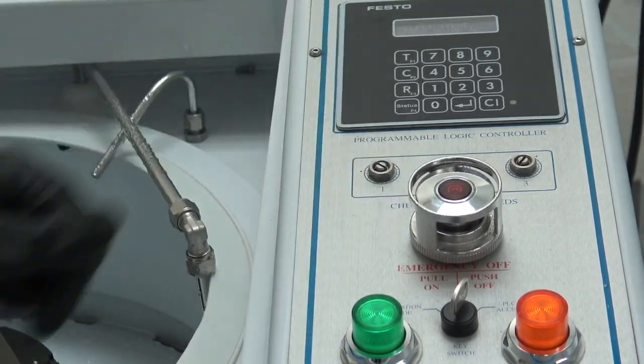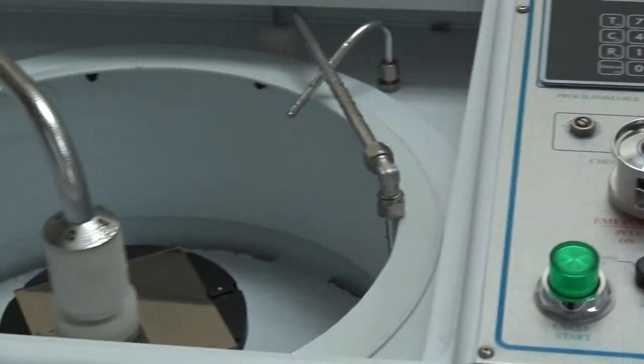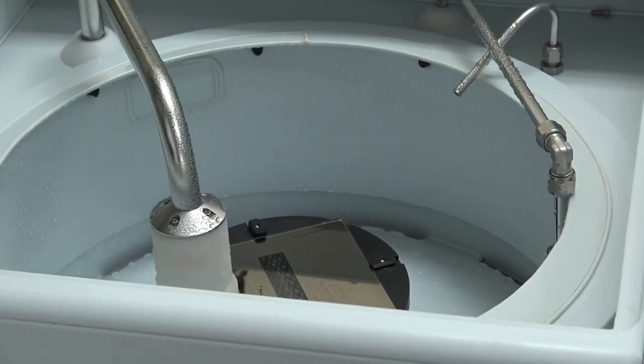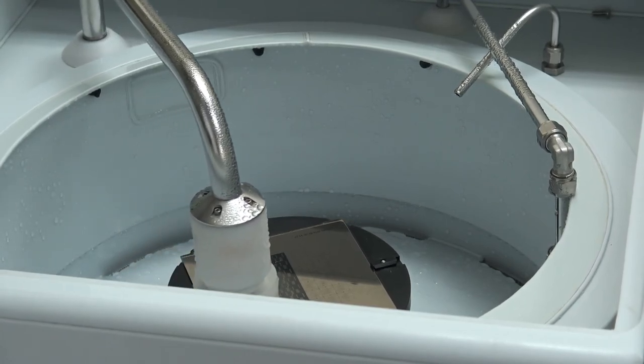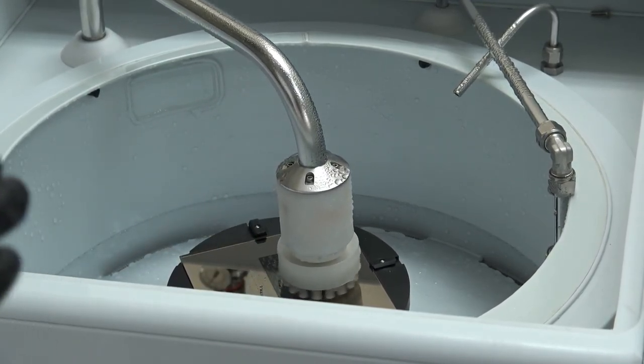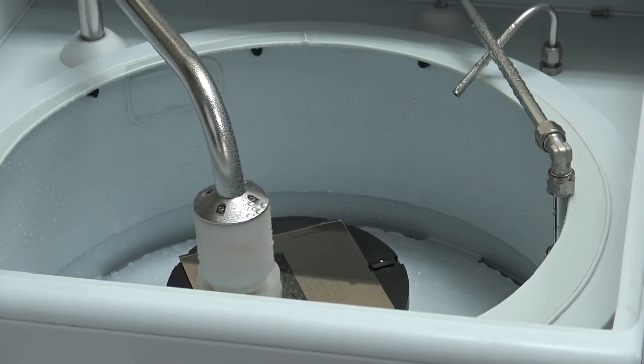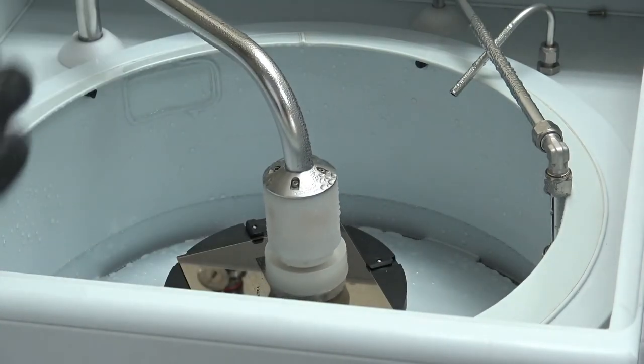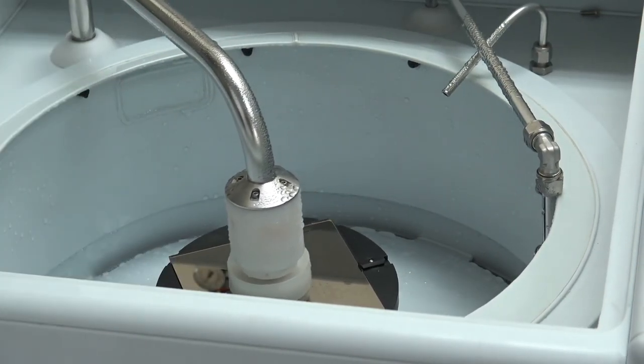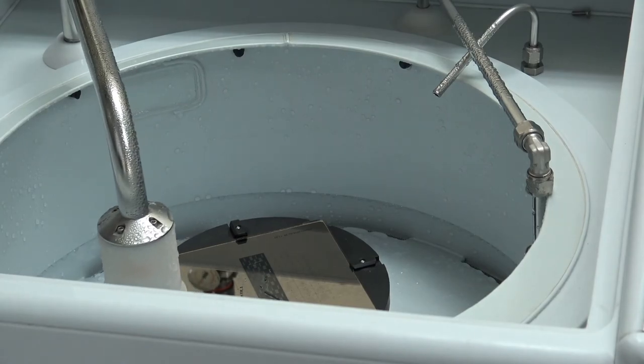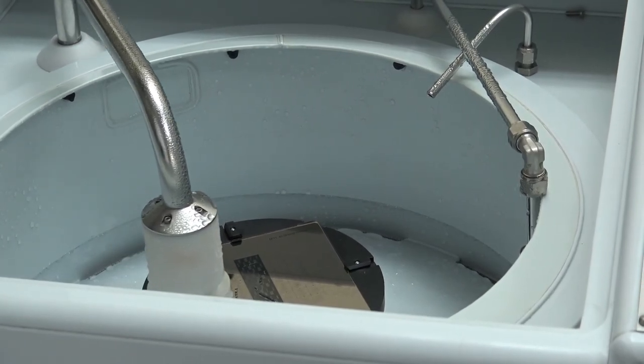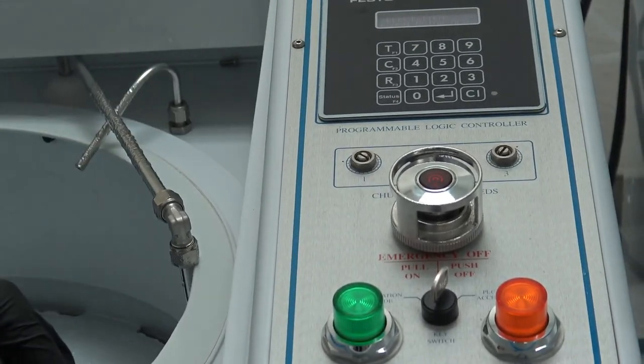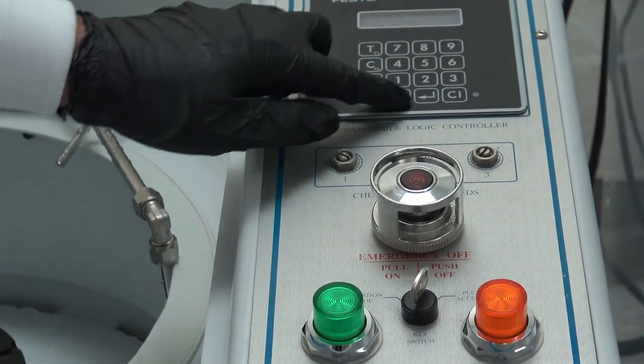Item number 7 is the brush motor. So now you can see that the brush is oscillating back and forth and rotating across the substrate. The brush doesn't make direct contact with the mask and substrates. It just comes within a few millimeters so that the friction between the brush, the solution of surfactant and DI water, and the substrate is enough scrubbing to effectively clean the surface. So that was number 7. Just turned the brush motor off.